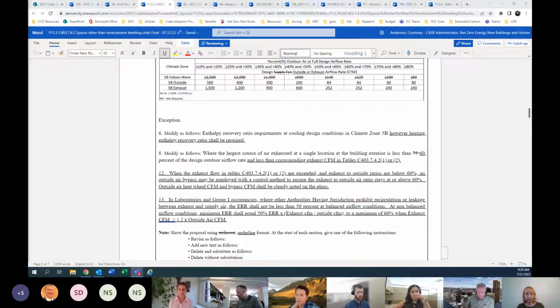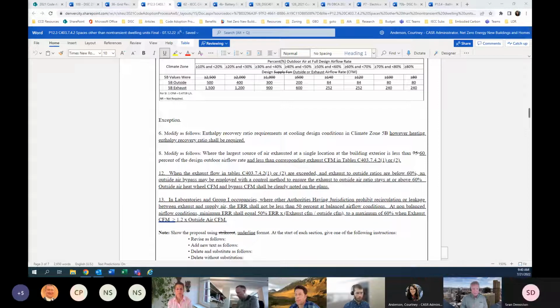And Mike, I concur with you on that. And we, by the way, we have kind of worked together. Mike did bring in stakeholders throughout his process here. Enthalpy in our climate, a regular selection, a good selection would be the same because, first of all, we're not required to do cooling. So therefore, there's no incentive to try to recover latent heat from the outside to the inside. If anything, it's a good thing to bring in all of our dry air. Okay, so a good selection would therefore be looking at the cold side of things, which inherently works out the same essentially, whether it's enthalpy or sensible.